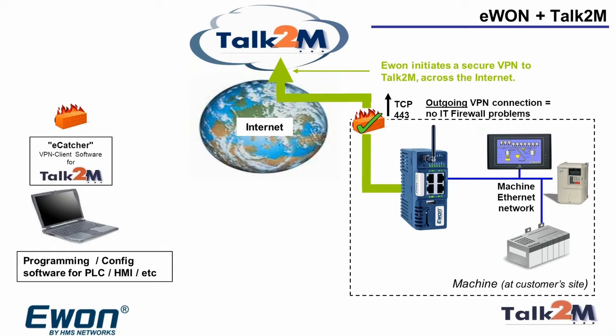The Ewon is making an outbound connection, an outbound VPN to the Talk2M cloud. So this green line here is a VPN tunnel. On the left-hand side, you have a laptop with some programming software, and the person that needs to access perhaps the PLC on the right-hand side launches his software called eCatcher, which is a VPN client software for Windows, which is living on that laptop.